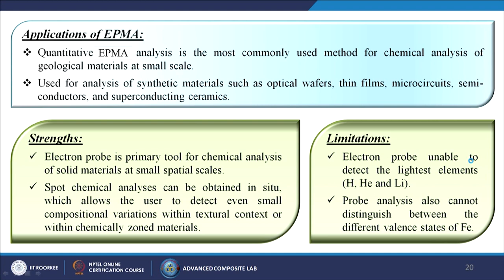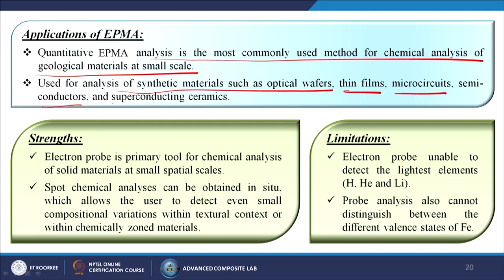EPMA applications: quantitative EPMA analysis is the most commonly used method for chemical analysis of geological materials at small scale. It is used for synthetic materials such as optical wafers, thin films, microcircuits, semiconductors, and superconducting ceramics. Strengths: it is primarily a tool for chemical analysis of solid materials at small spatial scales; spot chemical analysis can be obtained in situ, detecting even small compositional variations within textural context or chemically zoned materials. Limitations: electron probe cannot detect the lightest elements like hydrogen, helium, or lithium, and cannot distinguish between different valence states of iron.